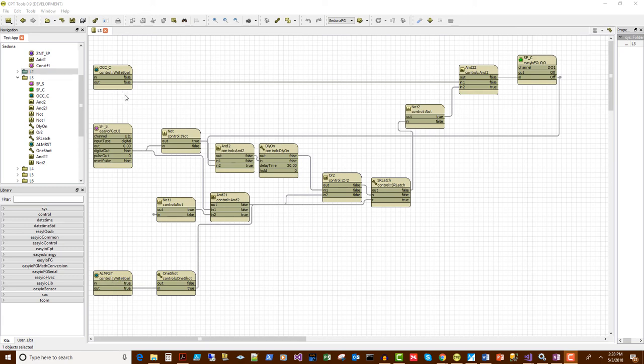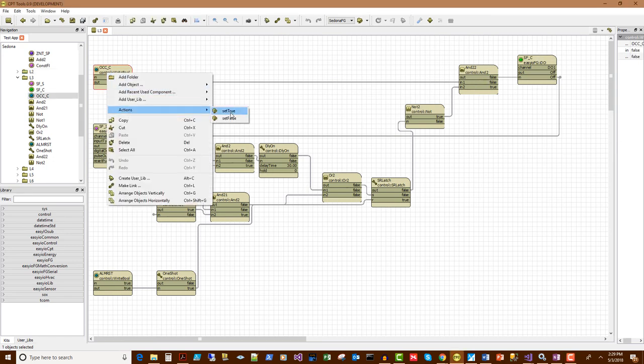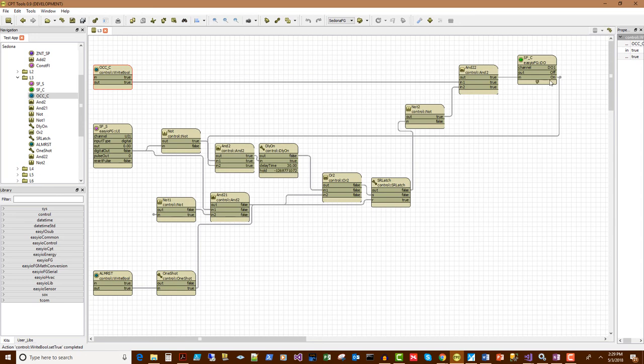Well, look at the code block. It's all right here. Occupancy command and the fan's not in failure. Great. Then the fan will be able to turn on. If, however, I turn on the fan and I don't have status, well, look at that. I don't have status and the fan's on.